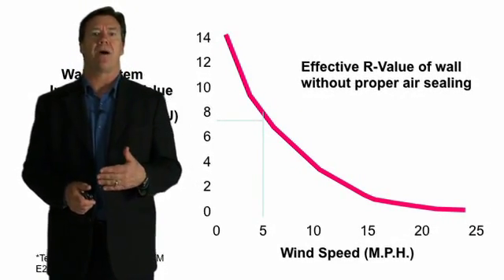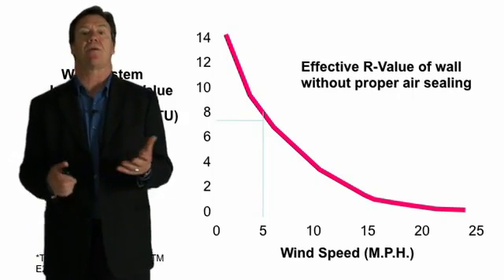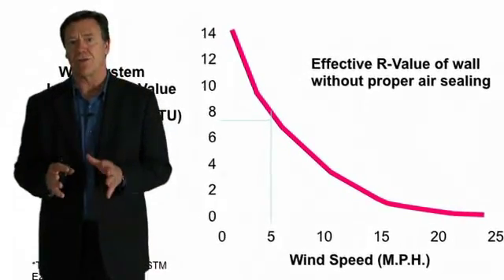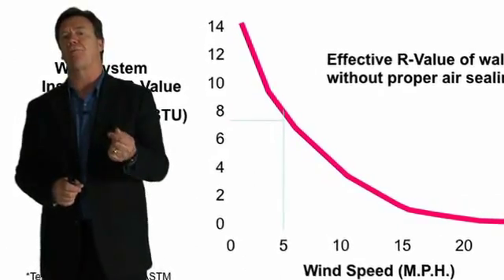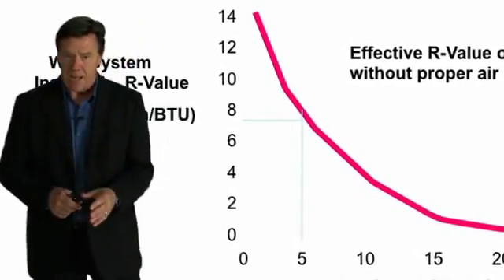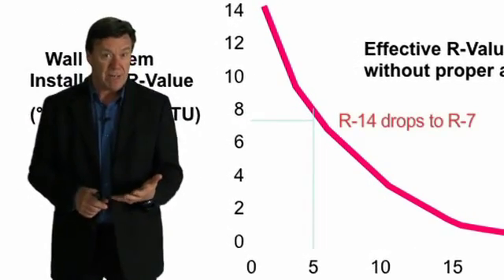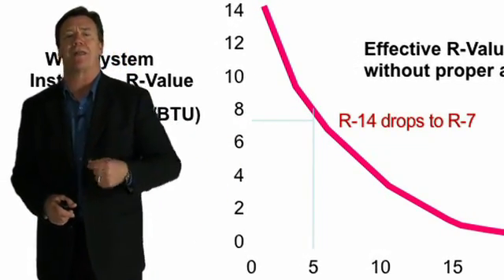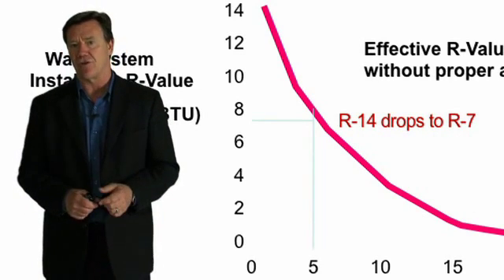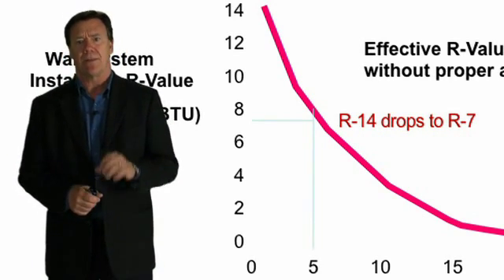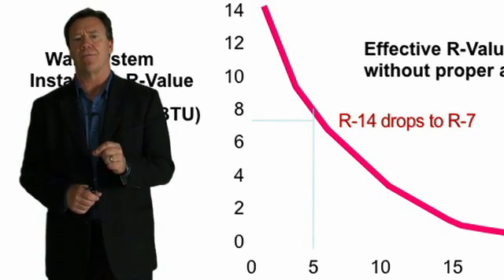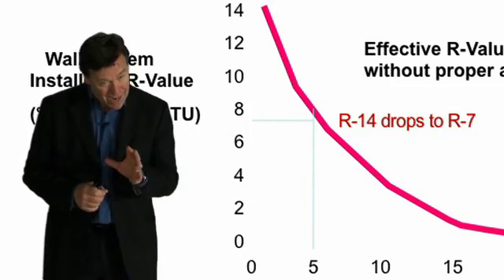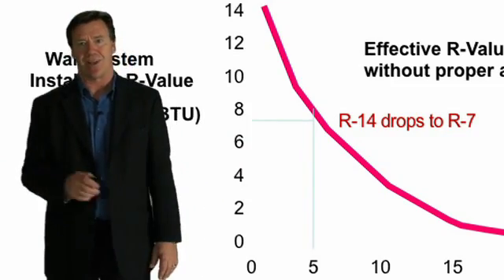For example, with a 5 mile-per-hour wind, unprotected insulation's R-value would drop from R-14 to R-7. So R-14 insulation exposed to even a 5 mph wind almost cuts its efficiency in half. That's why the code addresses air infiltration — not only to stop air from infiltrating through cracks and gaps, but also to protect the effective R-value of the insulation.